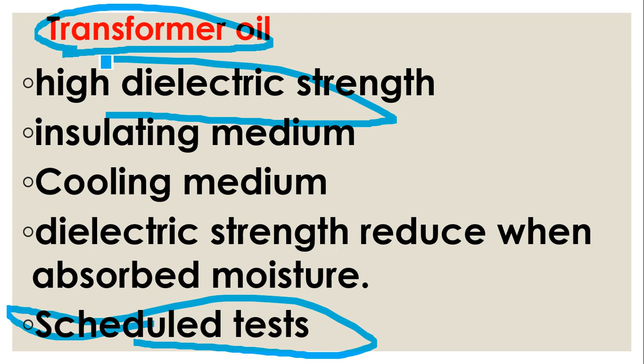One such test is the high dielectric strength test - the dielectric withstand test, also known as the breakdown voltage test or BDV test. The technician performs this scheduled test in the power station or substation wherever the transformer is available. Weekly or monthly, he takes out a bit of transformer oil and uses it for a few tests that indicate the condition of the transformer oil, whether it is good or not. So one of the tests is the BDV, breakdown voltage test.